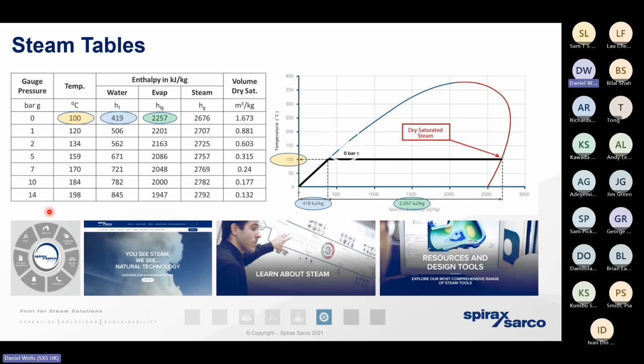The first two columns, we've got that pressure-temperature relationship. By understanding the pressure of the steam, we know its temperature, and vice versa. If we need to achieve a particular temperature, we can achieve that by nothing more than manipulating the pressure. It's why those very, very simple two-port spring-acting pressure-reducing valves are so useful to us in controlling the steam. But it also tells us why we need a good number of pressure gauges around the infrastructure. Without those pressure gauges, we don't have any understanding of what's actually happening in the steam system.